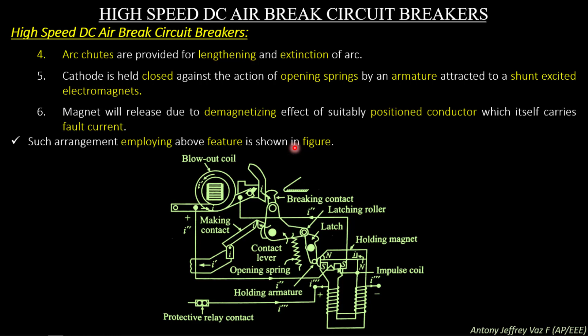The mechanism uses two sets of contacts for making and breaking respectively. So this is the main contact which is held with the blowout coil, and this is the other contact. Here you can see the lever and the latch system, which ensures the breaking contact. When the lever is in this position, it will connect the two conductors of the circuit breaker through the closed path like this. The breaking contacts, which are in series with the making contacts, close fast and are therefore ready for the tripping operation before the making contacts close.